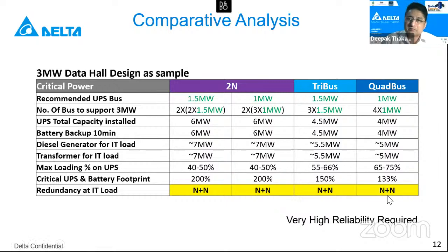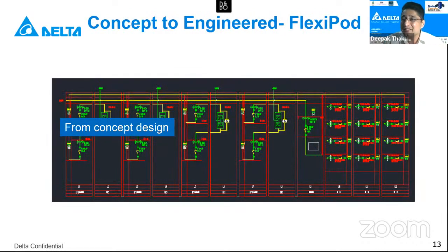to your end customer rack. Now, what can Delta support here? We have a concept of engineered solutions, which we call FlexiPod. Here, we work from the concept level of the electrical design with the customer. On the UPS front, we actually don't sell standard boxes. We design the UPS along with the integrated systems for the customer's requirement in terms of redundancy level, whether it is 2N, tri-bus or quad bus. And then we design this solution.